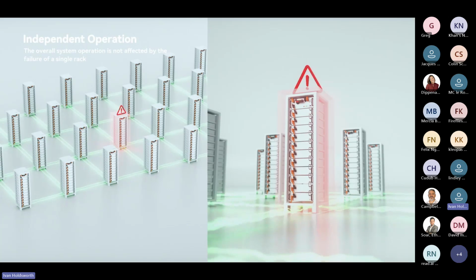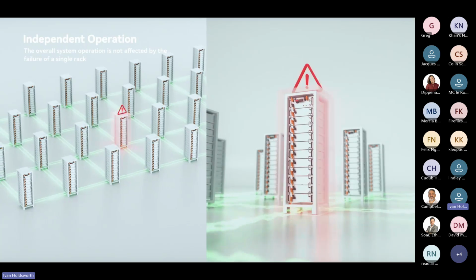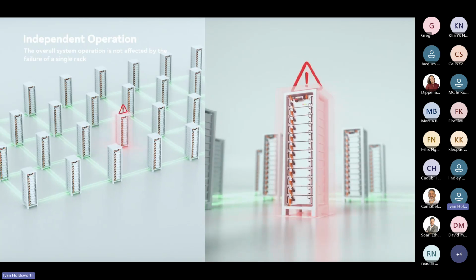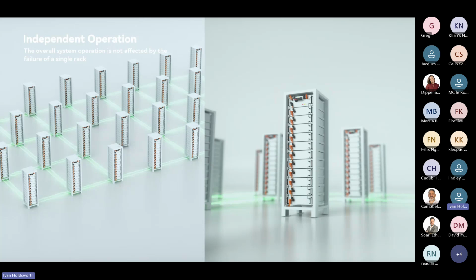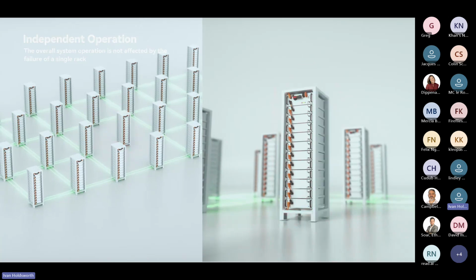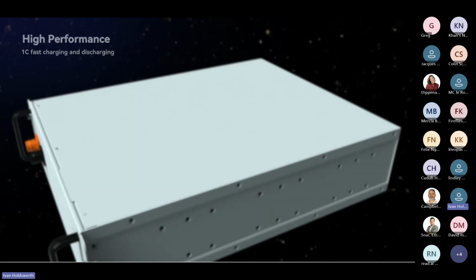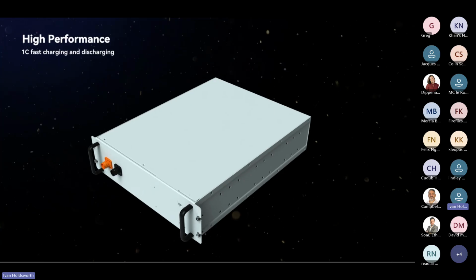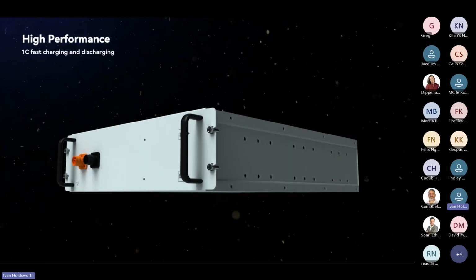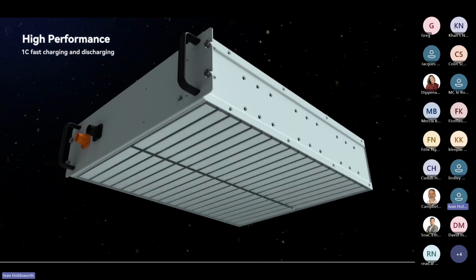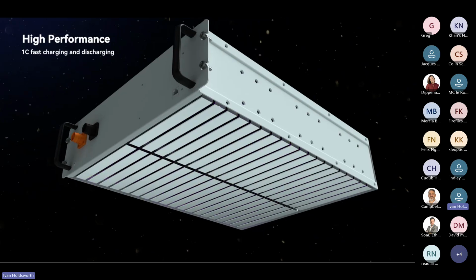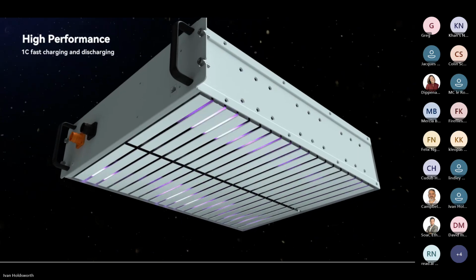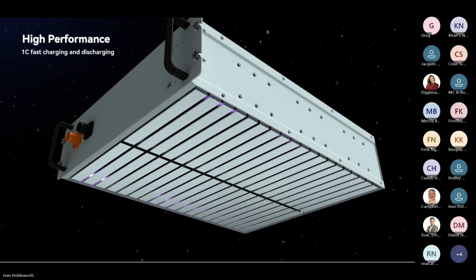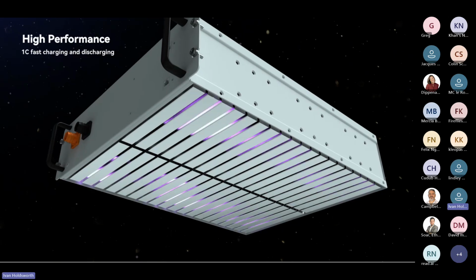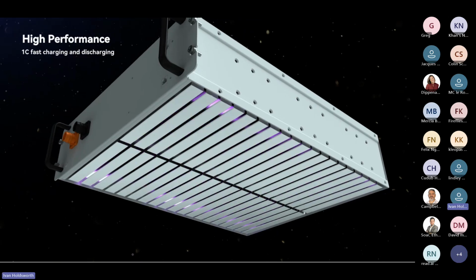And here we can see the Max Lite and its redundancy features. So if one of the towers stops working, the rest of the battery bank will keep working regardless of that one tower having an issue. And here we can see the Max Lite battery module, and you can see the 24 cells that are in the battery module. Each battery module is 7.5 kilowatt hours and 75 volts.